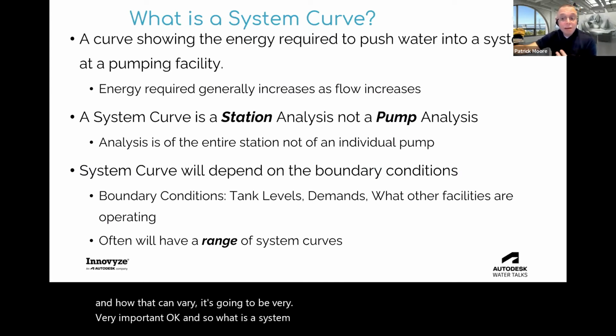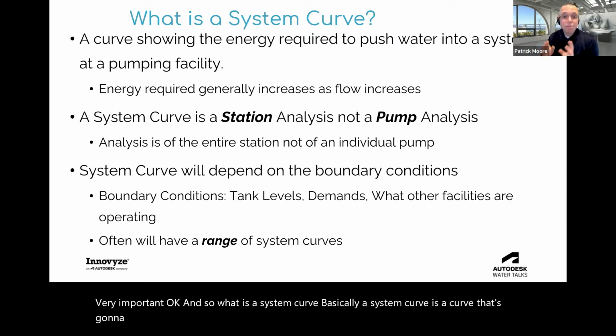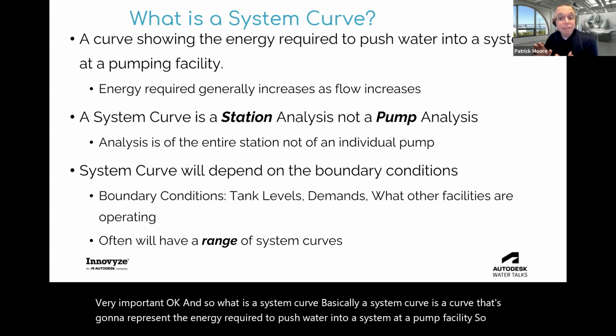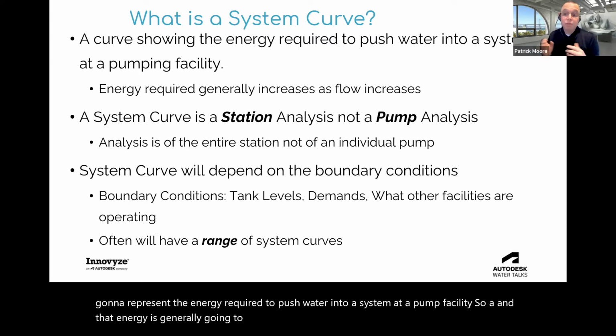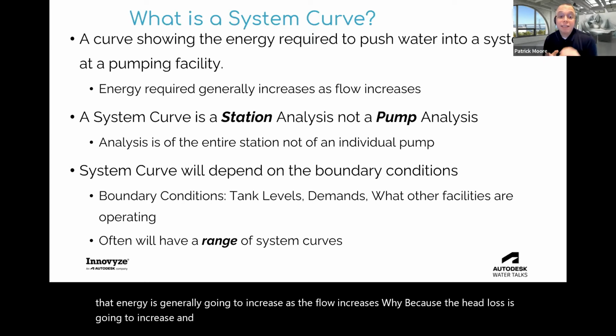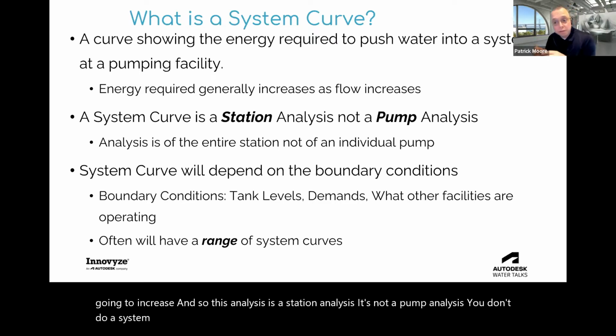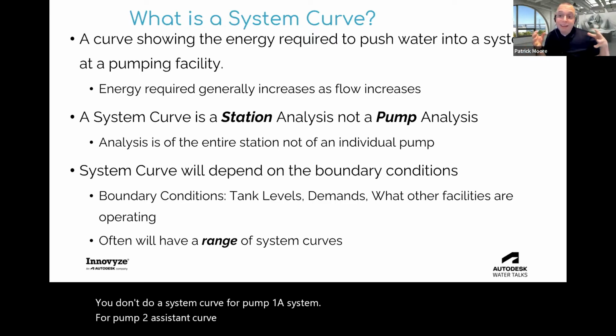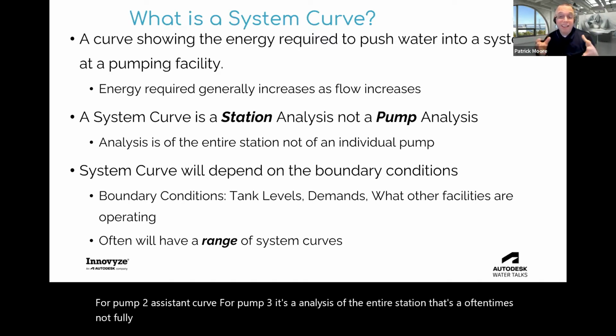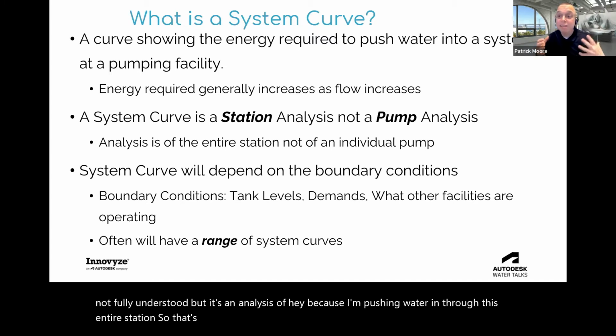Basically, a system curve is a curve that's going to represent the energy required to push water into a system at a pump facility. That energy is generally going to increase as the flow increases. Why? Because the head loss is going to increase. And so this analysis is a station analysis. It's not a pump analysis. You don't do a system curve for pump one, a system curve for pump two, a system curve for pump three. It's an analysis of the entire station. That's oftentimes not fully understood, but it's an analysis of, because I'm pushing water in through this entire station. So that's not a pump analysis, it's a station analysis. Okay, so that's very important to understand.